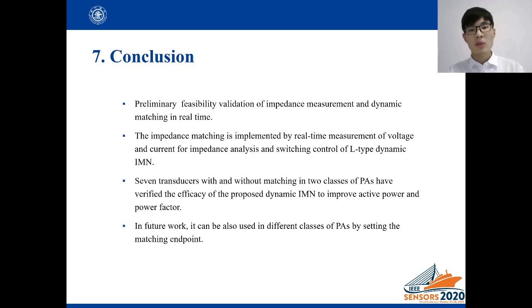Seven transducers with and without matchings in two classes of power amplifiers have verified the efficacy of the proposed dynamic impedance matching network to improve active power and power factor.